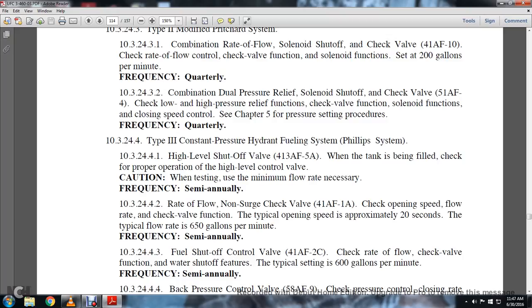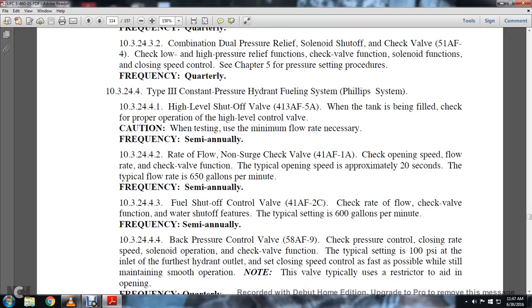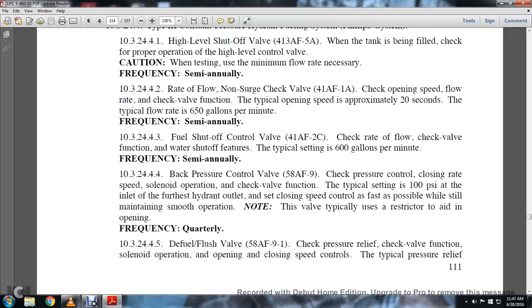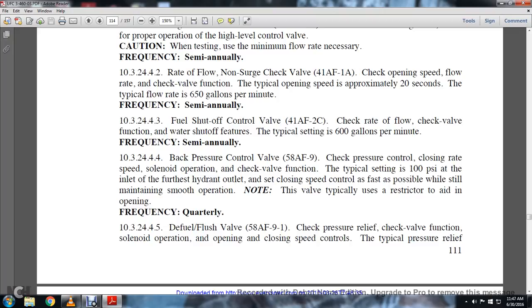The fuel shutoff control valve: check the rate of flow, check valve function, and water shutoff features. The typical setting is 600 gallons per minute, inspected semi-annually. The back pressure control valve: check the pressure control, closing rate, solenoid operation, and check valve operation. The typical setting is 100 psi at the inlet for the hydrant outlet. Set the closing speed for the control as fast as possible, while maintaining smooth operation. Note, this valve typically uses a restrictor to aid in opening.